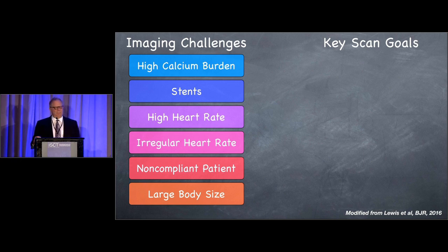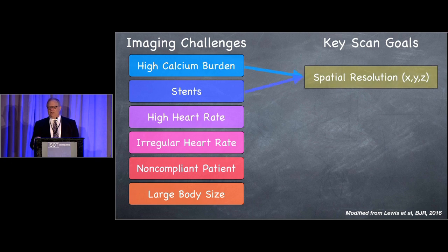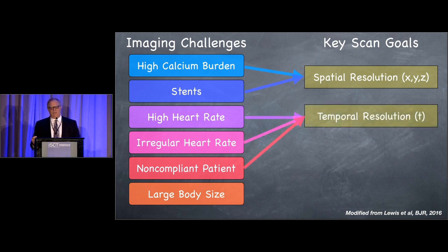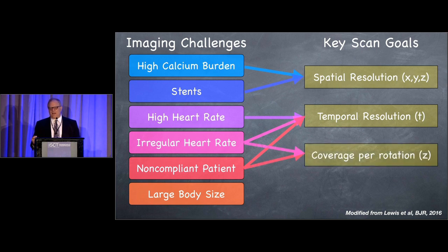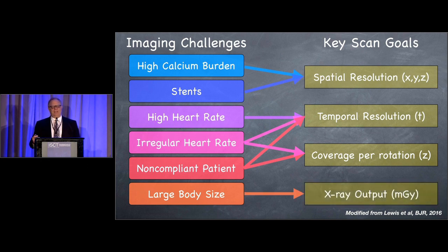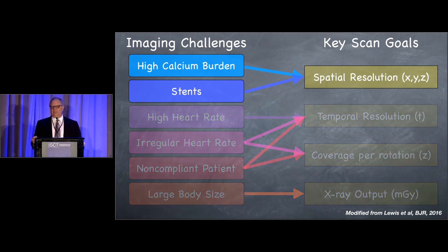These are some of the imaging challenges we face based upon the patients that present themselves to us. Particularly challenging are people with high calcium burden, people who come with stents, people with a high or irregular heart rate, non-compliant patients, and large patients. High spatial resolution would help with stents and calcium burden. High temporal resolution is what we need for high and irregular heart rates. A high degree of coverage per rotation and high X-ray tube output are also key properties.